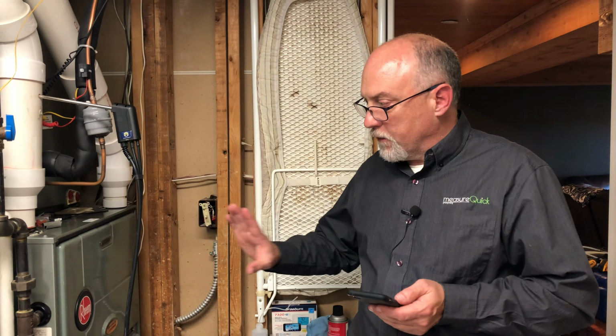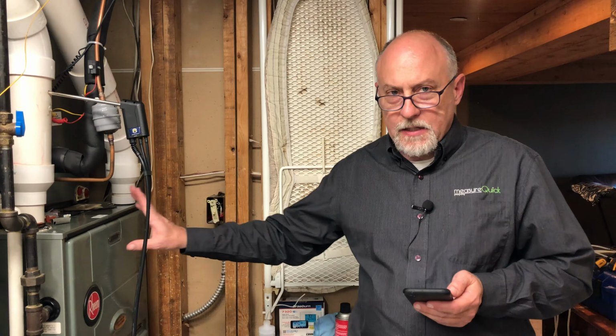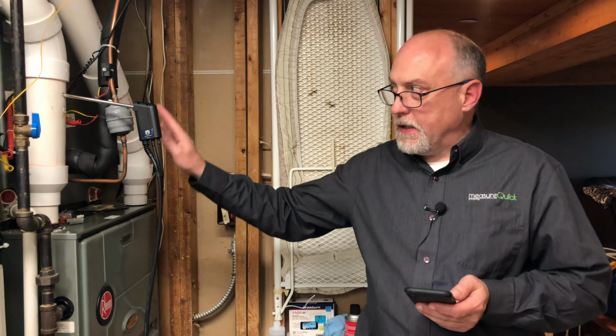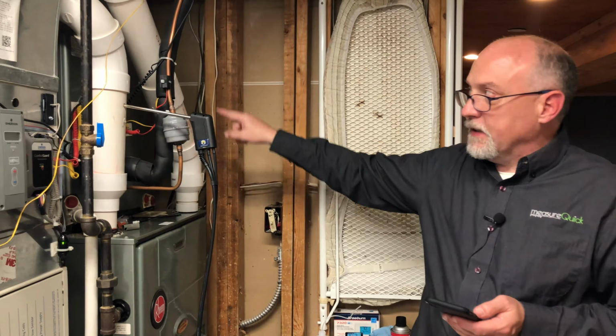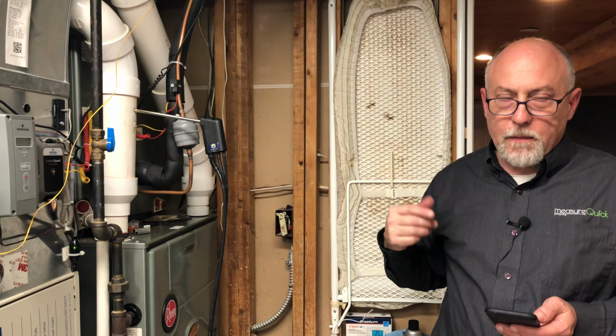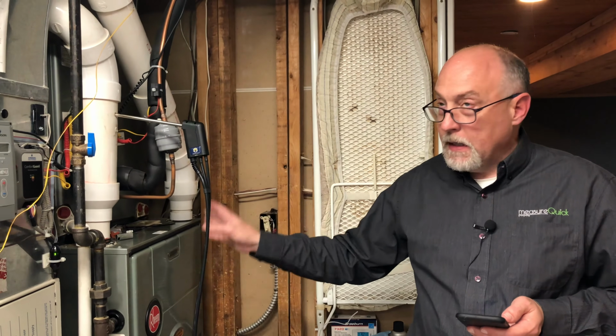All right, so now that we removed all the meters, got the manometers off, and we got the furnace all buttoned up again, because I adjusted the fuel pressure on this furnace, I really need to do one more combustion test with the blower door on. Remember, this appliance is getting its air from outside, so we want to make sure that when the door's on, it doesn't affect the combustion efficiency. And again, this goes back to testing the venting system. So if there's like leaves in the outdoor vent and I had the door off, I would never detect that there's a combustion problem until I put this door back on.